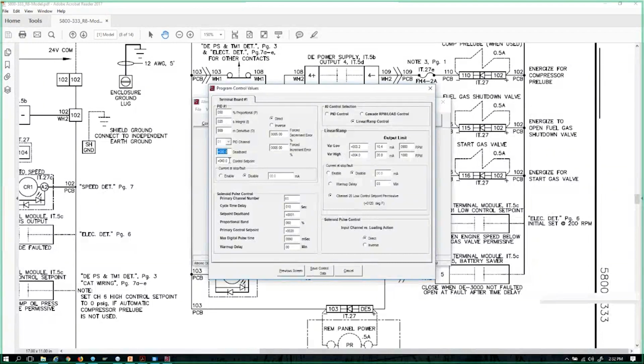So that could tend to get me into a problem where I'm having too much of a sweep or too much of a differential, and I could for sure overpressure. So again, usually in most situations, in most applications, if I'm tuning one of these in the field, if the target pressure is less than 100 pounds, I'm going to have 0 selected as a deadband.